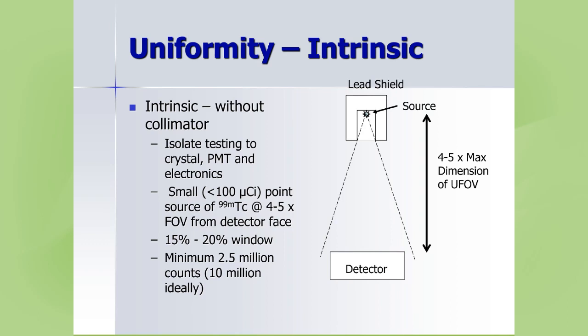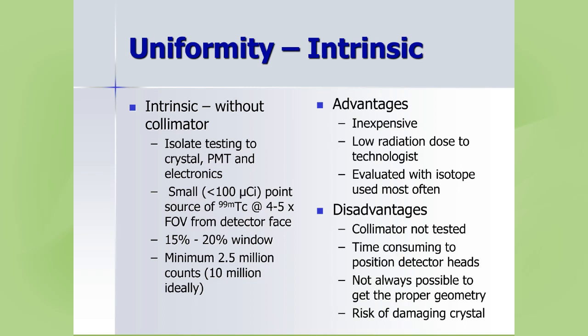Advantages of intrinsic testing: relatively inexpensive, low radiation dose, and tests the camera system with the isotope most commonly used clinically. Disadvantages: the collimator is not in place, which isn't the clinical situation; it can be time-consuming to position detector heads properly; getting five field-of-views away may not always be possible; and there is risk of damaging the crystal once the collimator is removed.